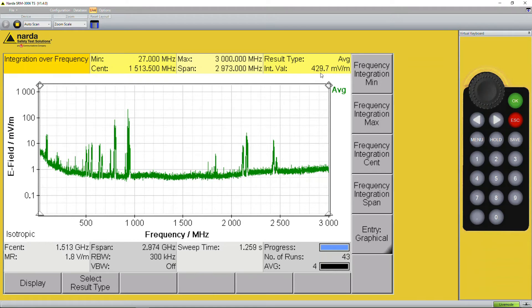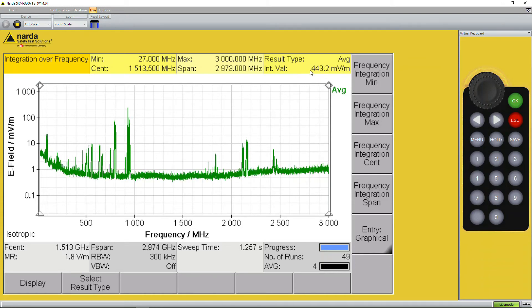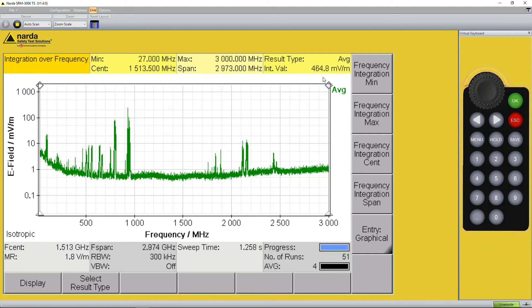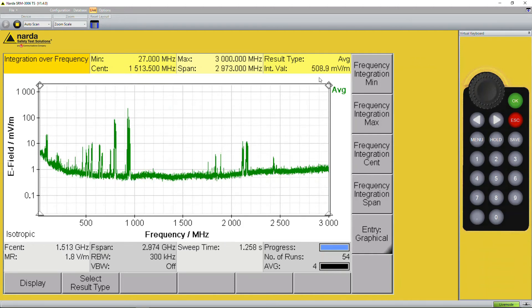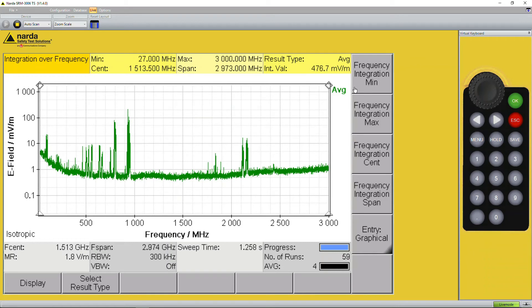Again you can see it's fluctuating because it's a live signal, around 440 to 460 millivolts per meter. So this is now like a broadband measurement between 27 megahertz up to 3 gigahertz.